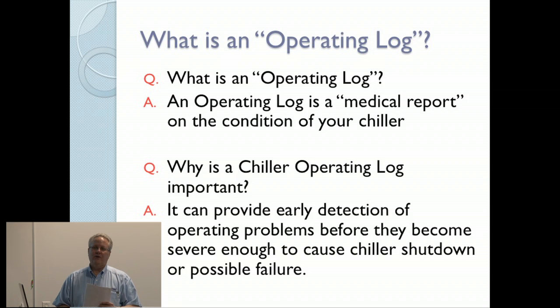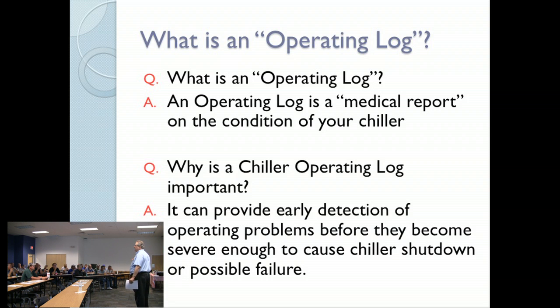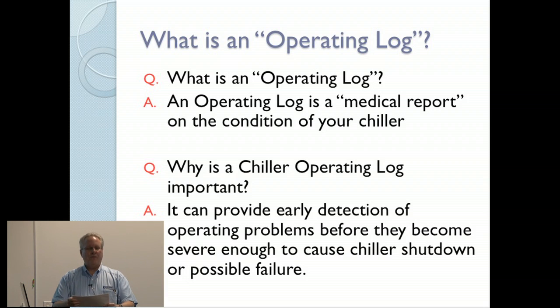The story from years ago that I had heard was a contractor got a call from one of their customers, and there was water all over their chiller room floor. And when they got out there, they found that they had froze the evaporator. And they said, geez, I don't know how this happens. We're logging the chiller every day. And sure enough, they had a custodial person go out, and they instructed them how to take numbers off and write everything down. And when you look at the log, you saw on the evaporator water temperature each day, 38, 35, 32, 28, 26, 26, 26. He was just told to write the numbers down, not to think about them.